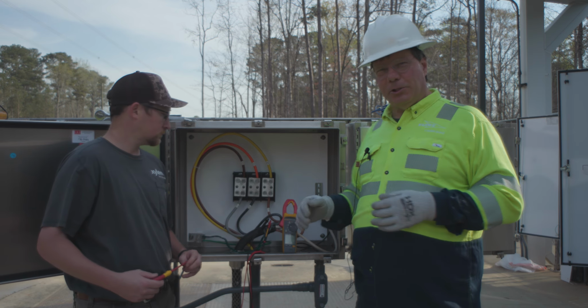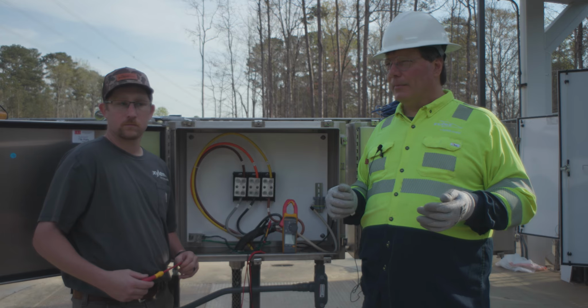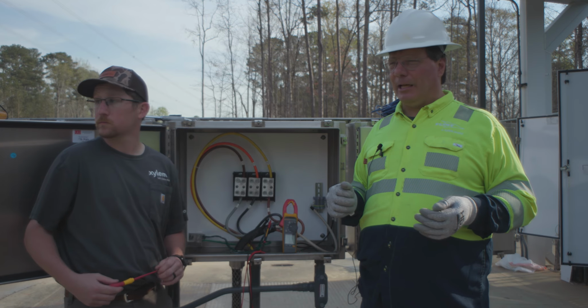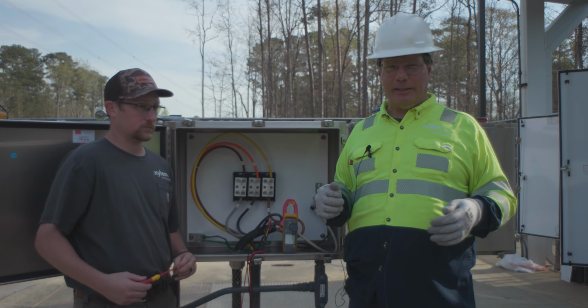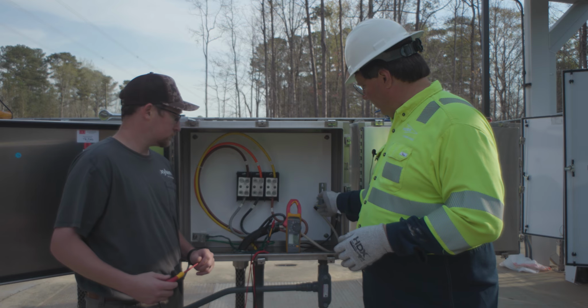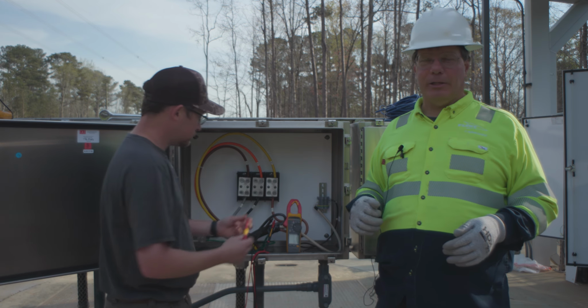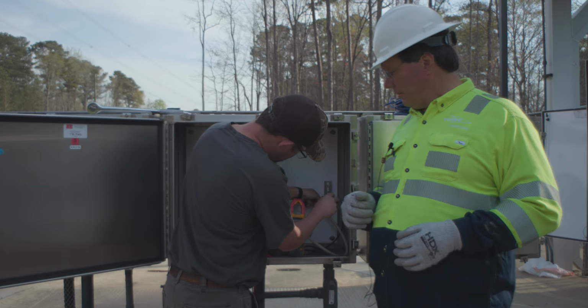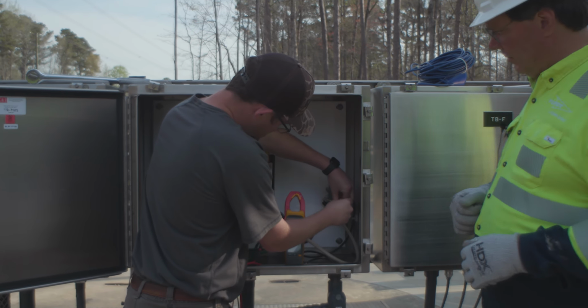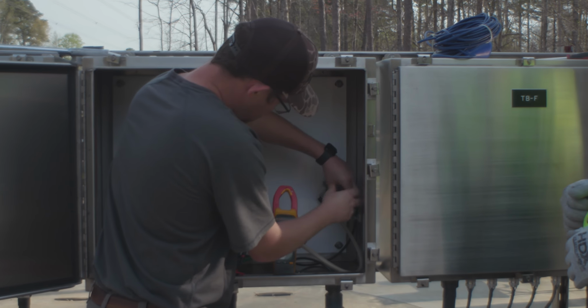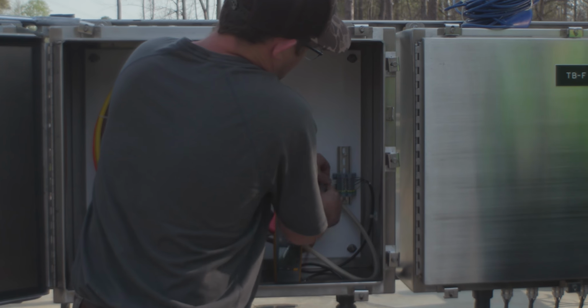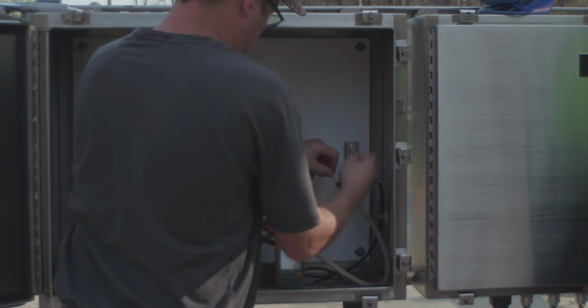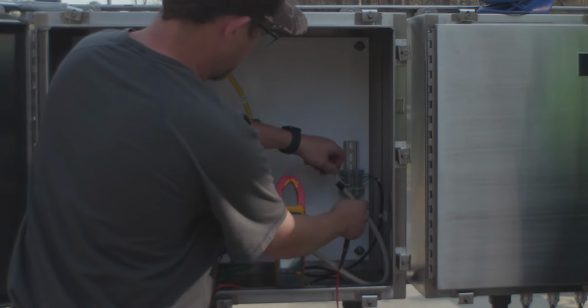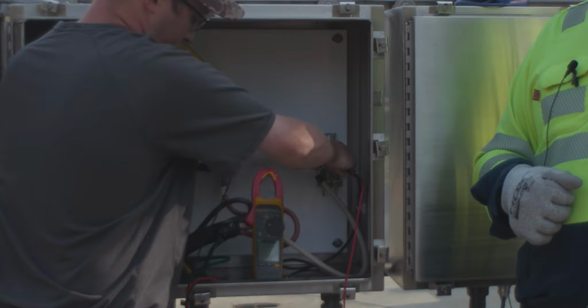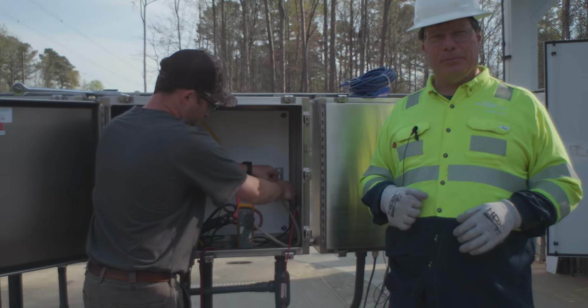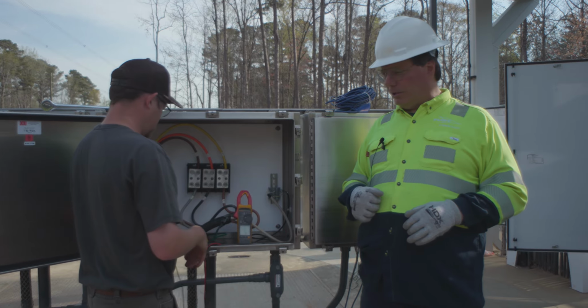But we're not going to check 1 and 2 because it's very high ohm. It's anywhere from 40 to 80 to 100 and something ohms, depending on what state it's in. But T3 and 4 should be somewhere less than 3 ohms. So we're going to check that real quick. Okay, he's reading continuity at 1.7 ohms. So T3 and T4 are good, so we'll put them back in service.